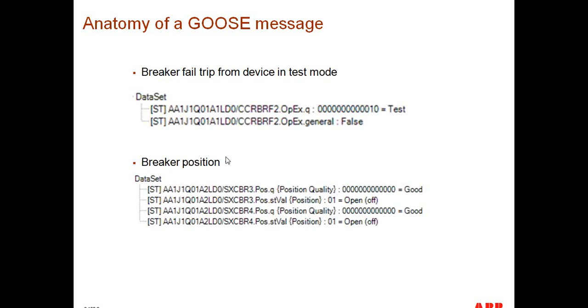This is another example of information to share, which is the position of the breaker. In this case, we see XCBR, the physical representation of circuit breaker instance number 3, position. The quality is good, meaning this device is not in test mode. Then we see the position. Position is actually 2 bits. It's what's called a DPS, double point status, so it could be 11, 01, 10, or 00. In this case, the device is reporting a position of 01, meaning the device is open, or in the off position. And then we have the same for XCBR number 4, which is just another breaker that this relay is reporting information to.